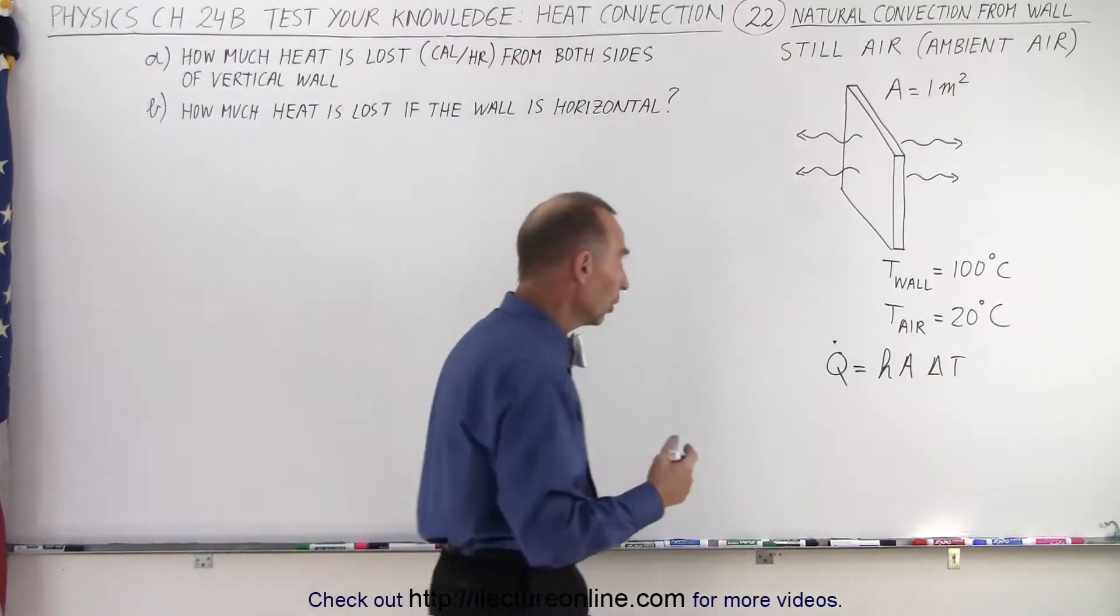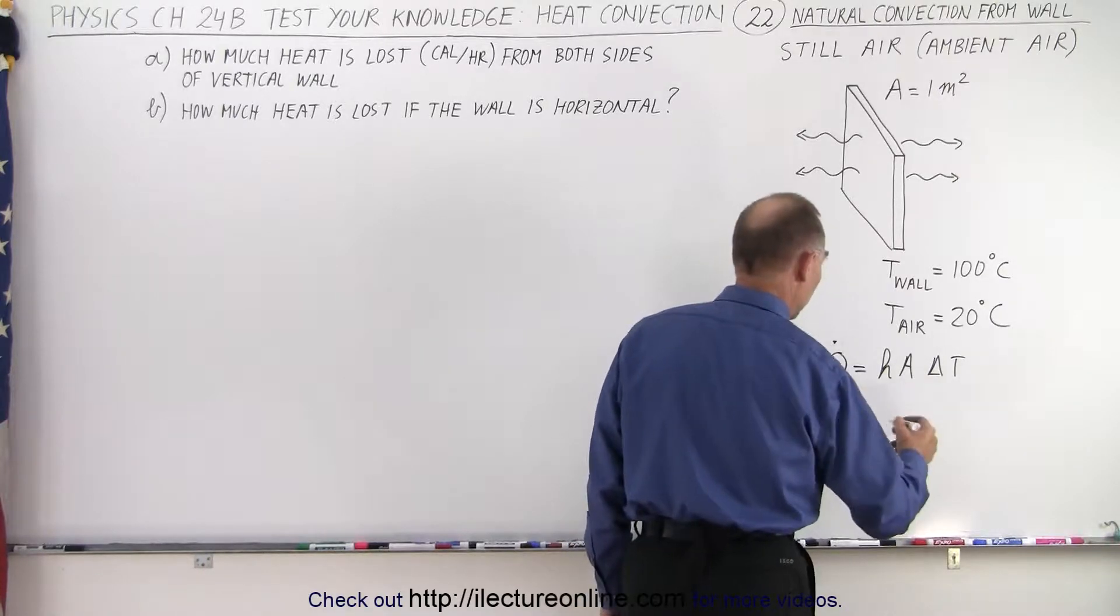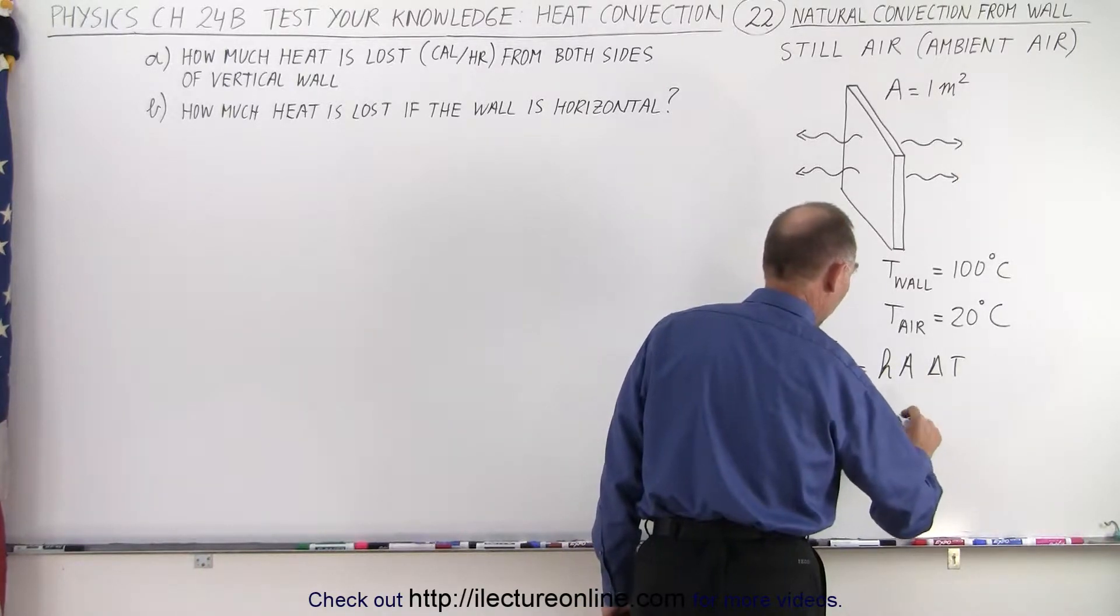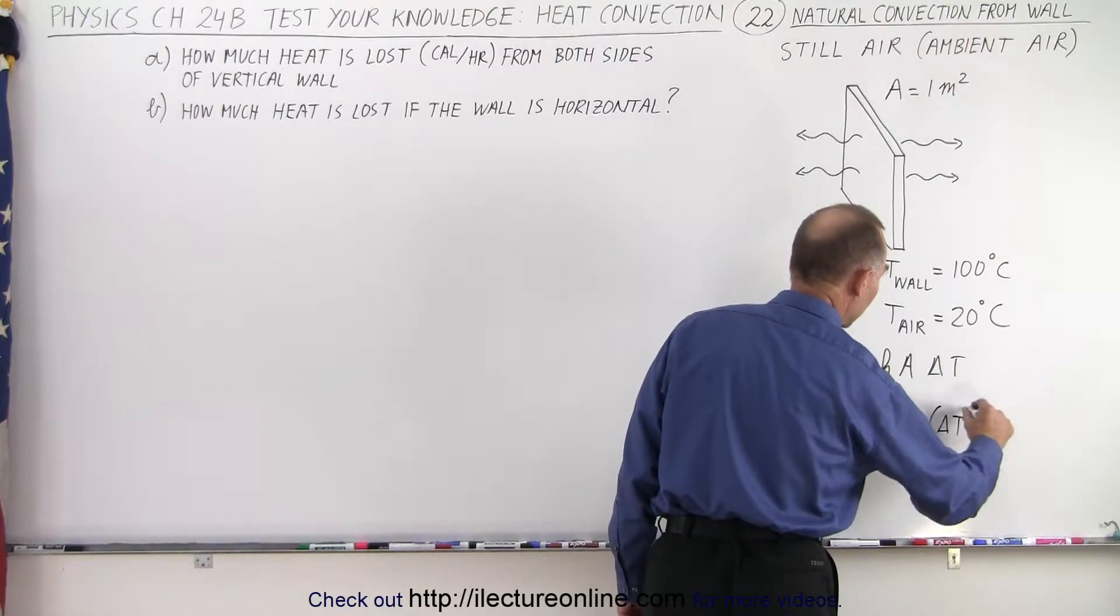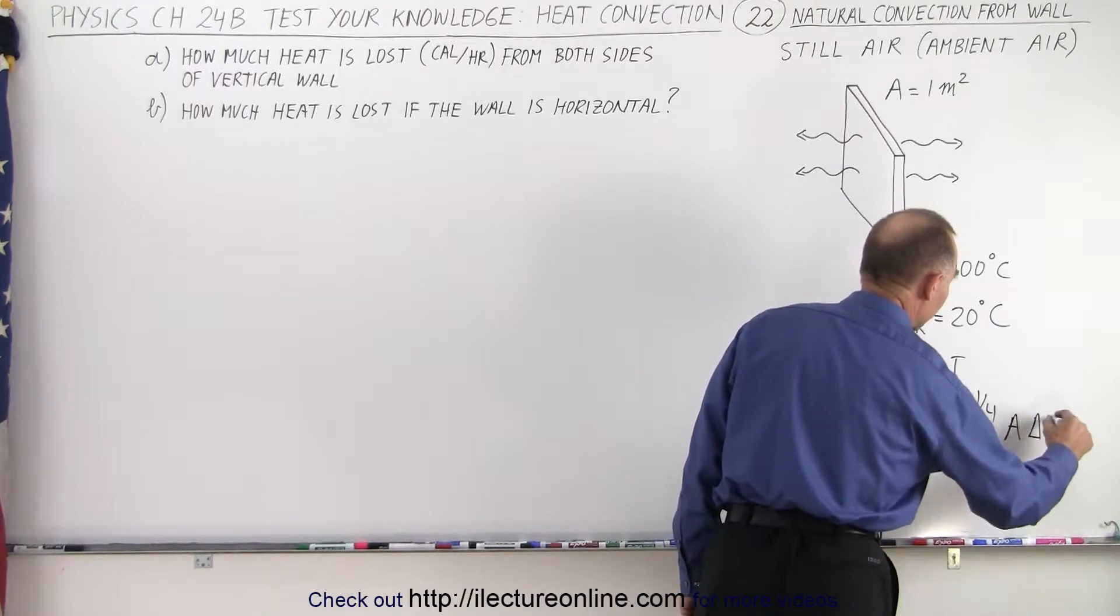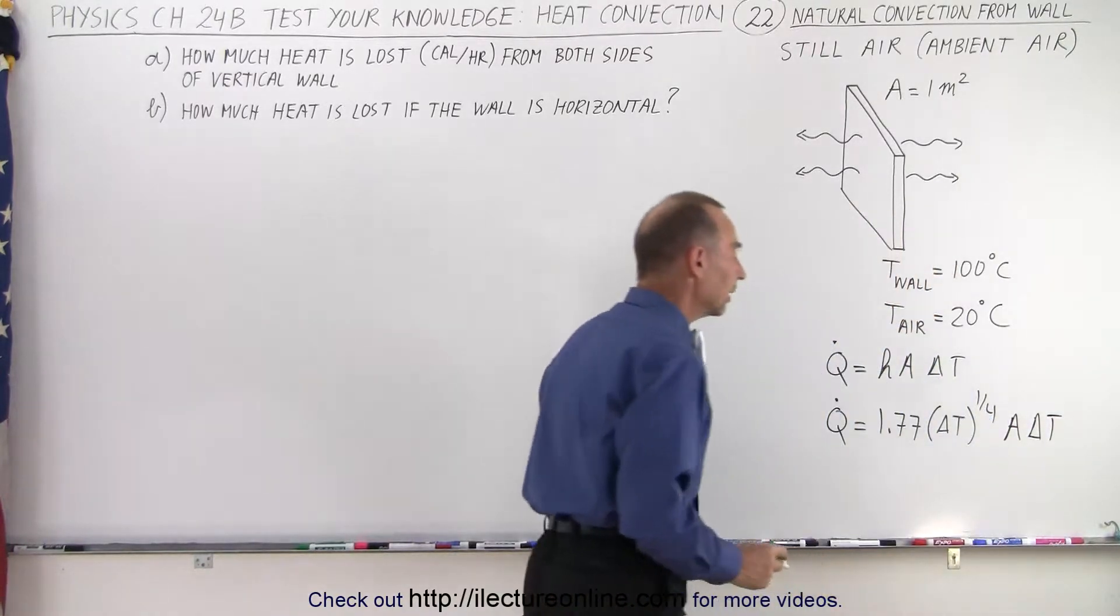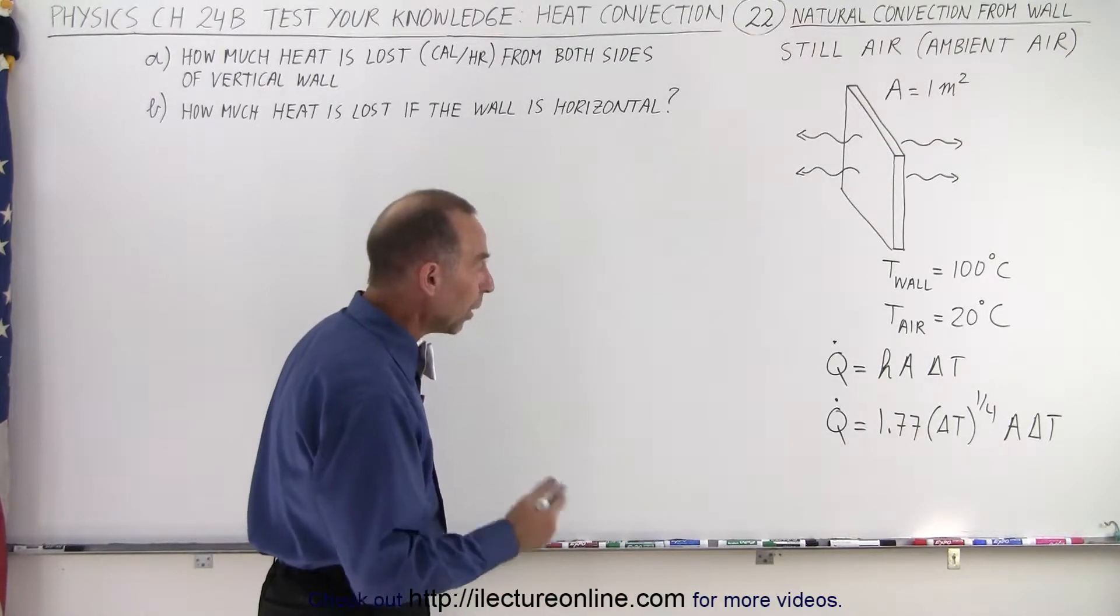And we can use an old equation, Q dot, which is still fairly accurate, where we can take H to be 1.77 times delta T to the one-quarter power, and multiply it times the area times delta T. And of course, that would be in terms of joules per second or watts.